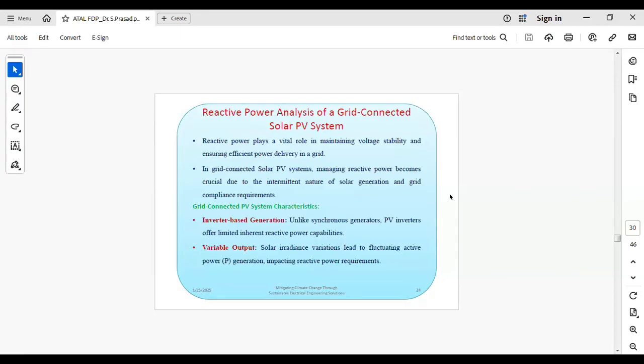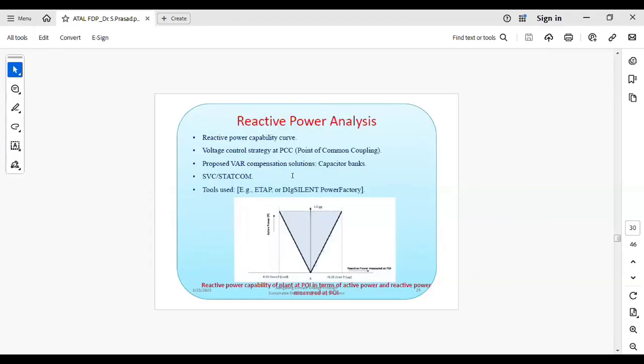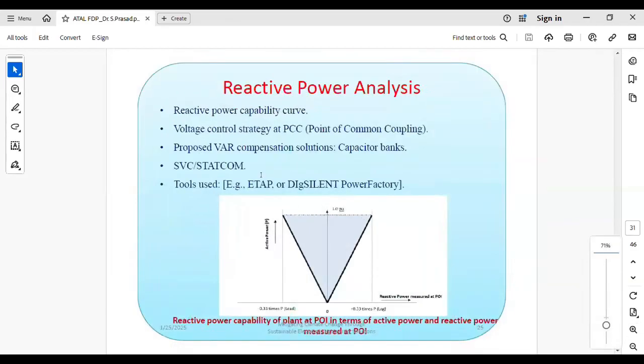So how much reactive power support must you have at the PV plant so that you do not violate this criteria? Therefore, we are conducting reactive power analysis at the point of interconnection. When you go for the reactive power analysis, you can see the reactive power capability curve. This is the most important thing: the reactive power capability curve of the PV plant at the point of interconnection. This is one of the most important tasks you have to verify. Whenever you plot this PQ capability curve of the PV plant at the point of interconnection, that curve has to lie outside this boundary. The shape you are seeing is a V shape.